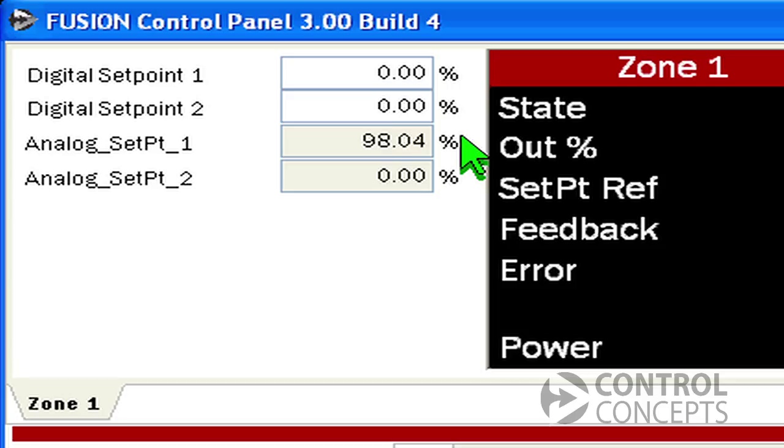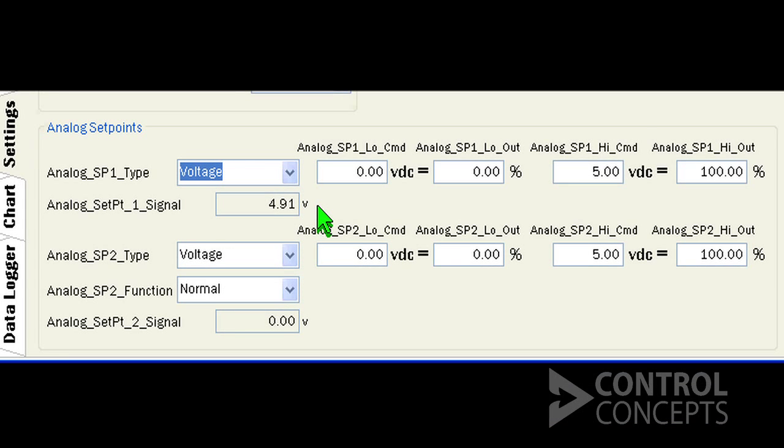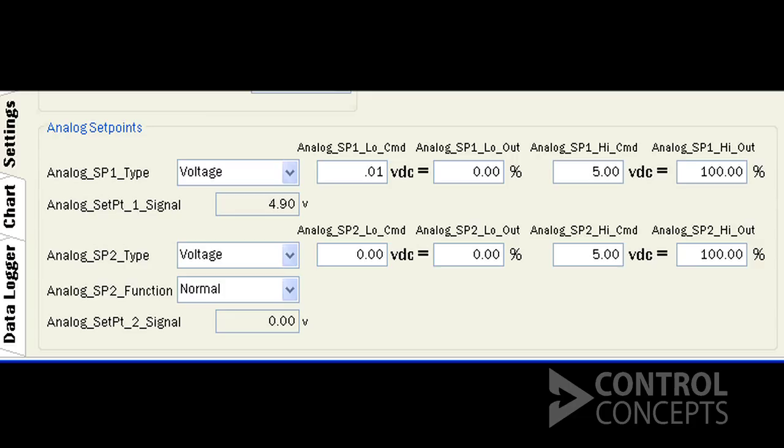With full on power we are only getting 98 percent. So to correct for these signaling errors we need to adjust scaling. Let's enter 0.01 as the off state value and 4.91 as the full on value.